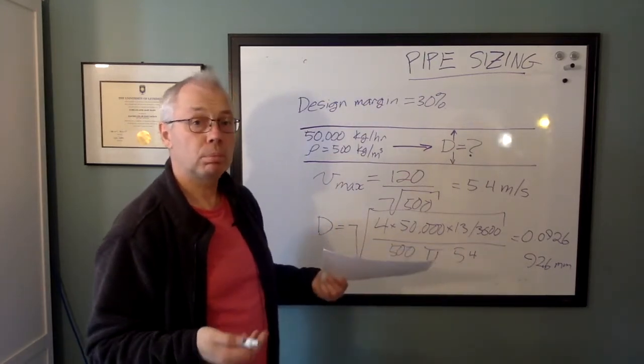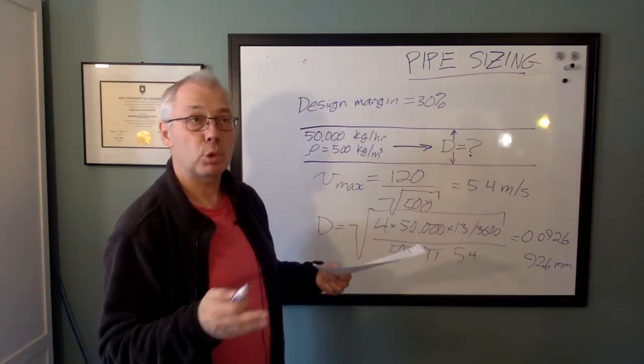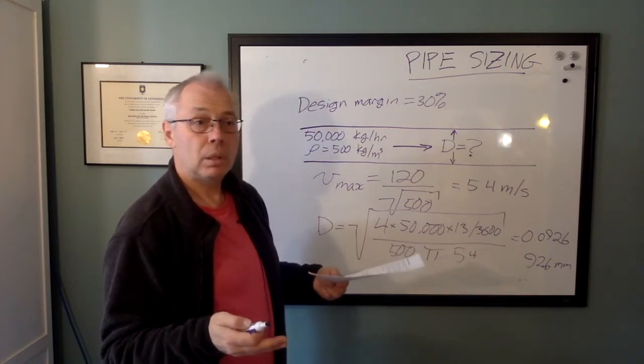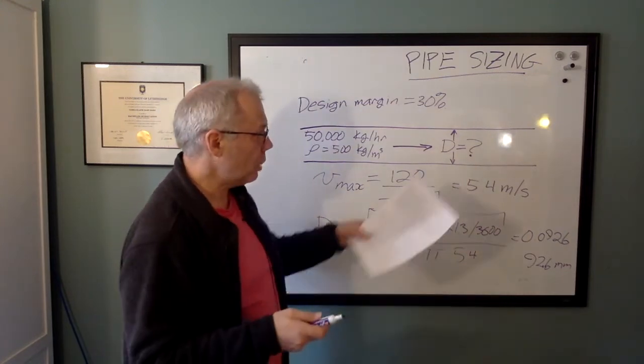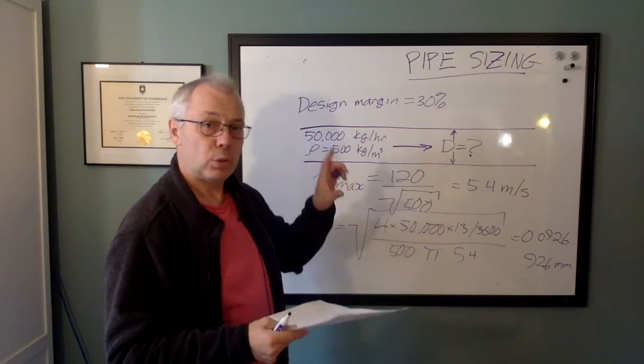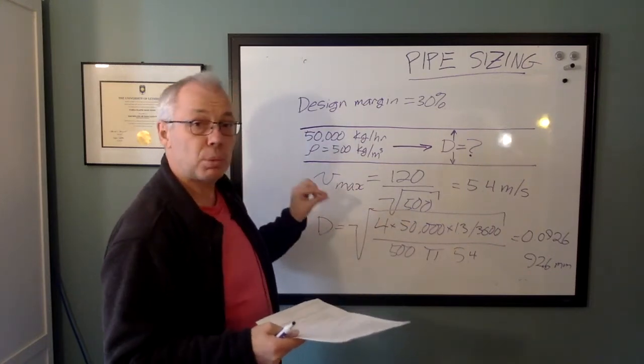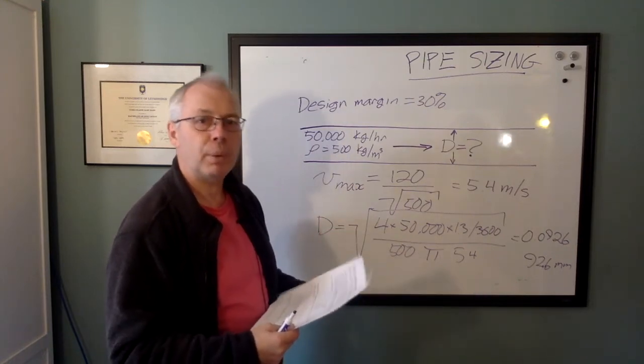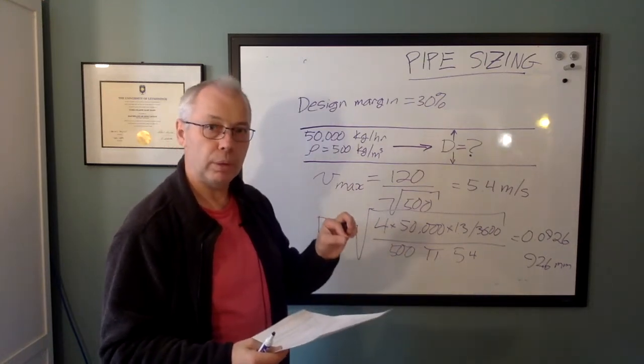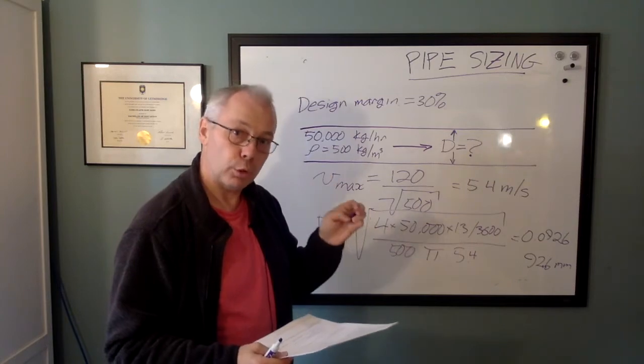So a 4-inch pipe, which has an inside diameter of just over 100 millimeters, will work just fine. It will give us the right velocity. So that would be the right pipe size using a maximum velocity as a criteria. That's criteria one. What about pressure drop? Let's take a look at that.